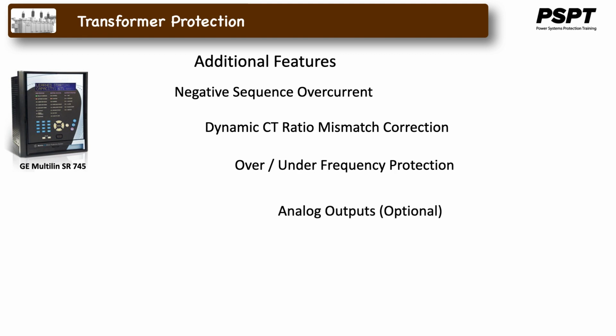Analog outputs, which are optional, include 7 transducer output channels allowing individually programmed outputs for ranges of 0 to 1 milliamp, 0 to 5 milliamps, 1 to 10 milliamps, 0 to 20 milliamps, and 4 to 20 milliamps. Channels are assigned to any measured parameter.